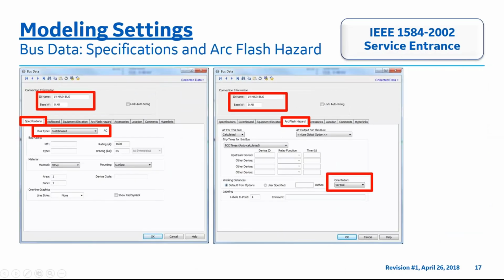The Specifications tab on the left-hand side. A person will create a base kV of 0.48 or 480 volts, in this case for a switchboard application demonstrated here. In the Arc Flash Hazard tab on the right, notice the Orientation pull-down menu. Notice that the default is vertical, which refers to the bus orientation in any piece of electrical equipment. Utilize this new EasyPower pull-down menu for the appropriate bus orientation for your distribution application, such as in switchboards and/or switchgear.